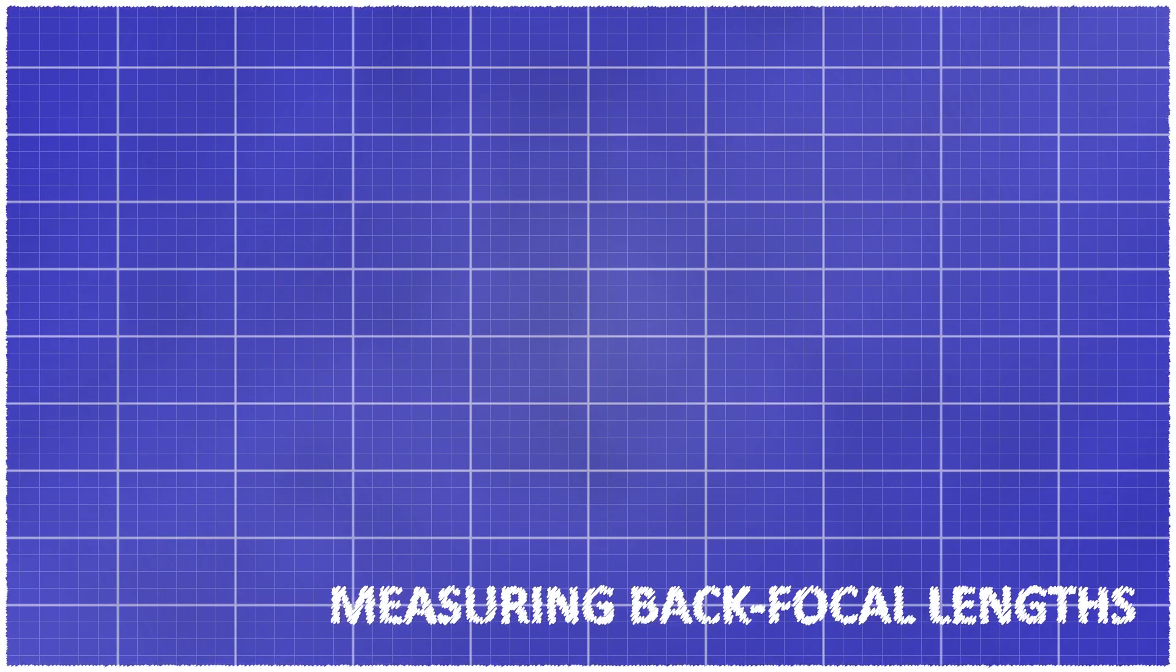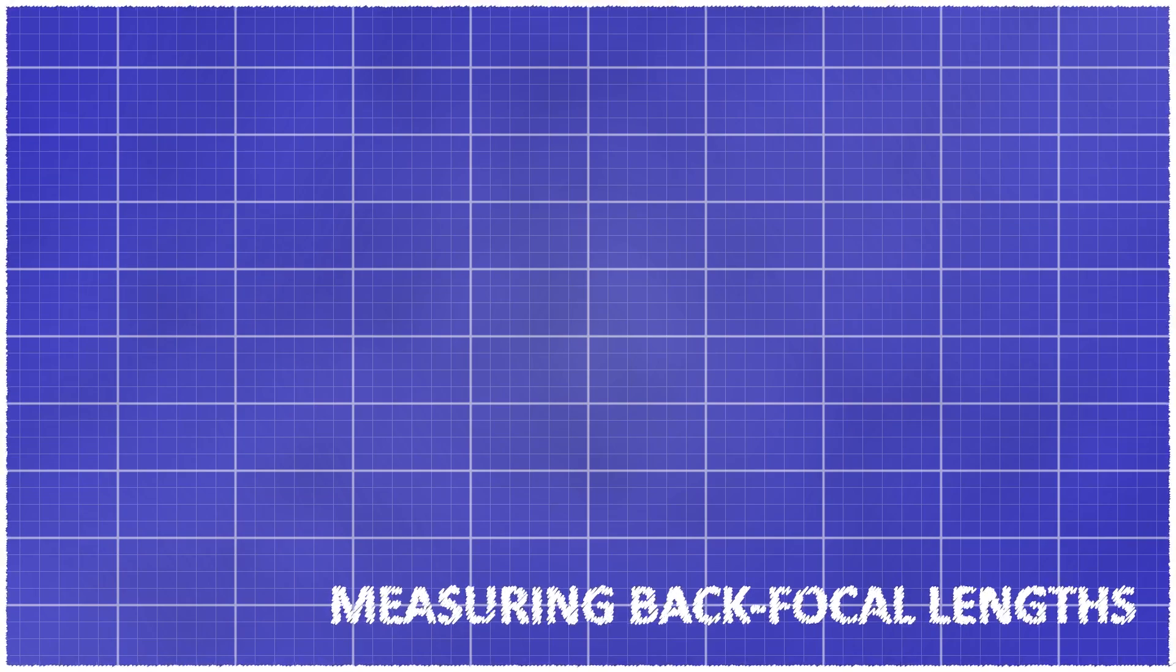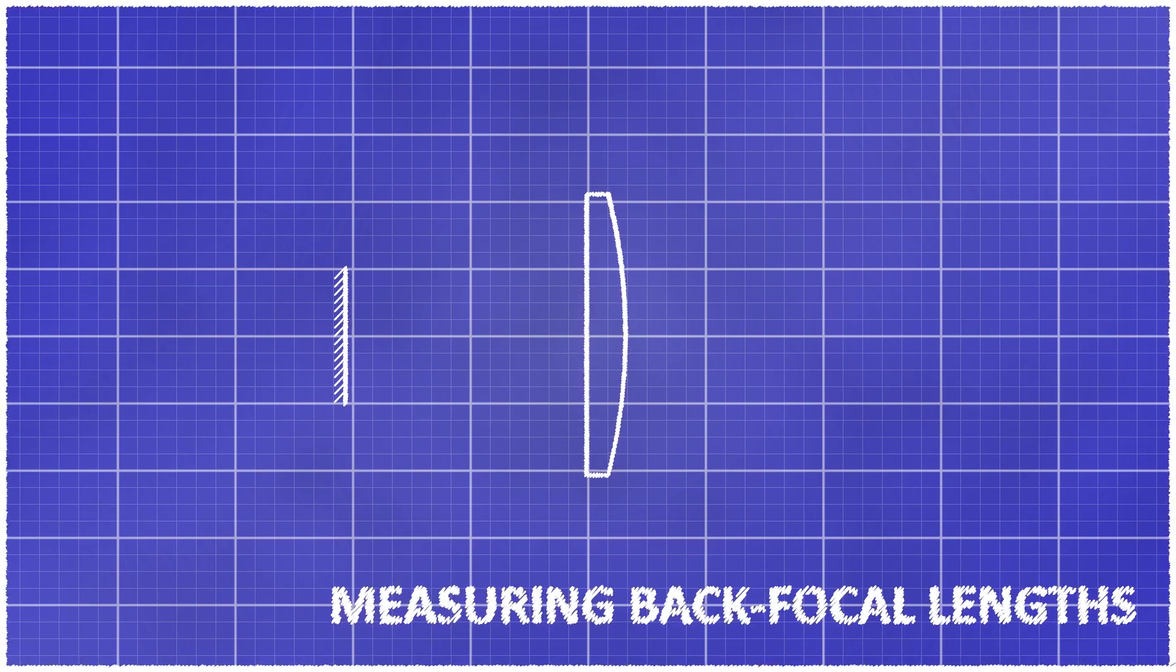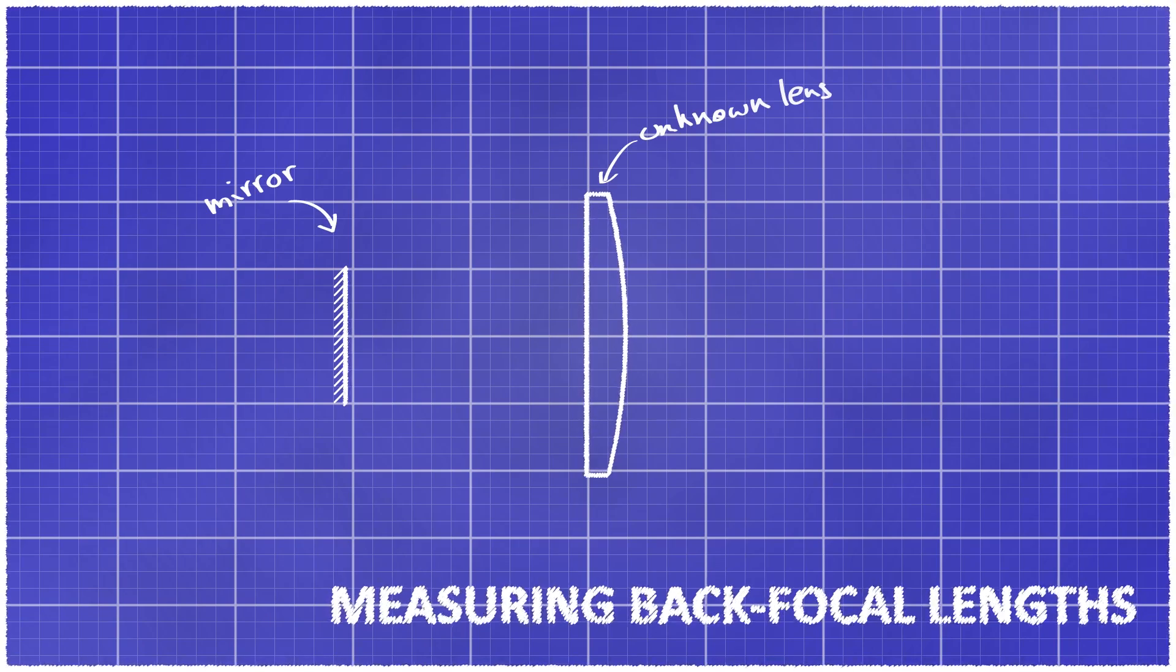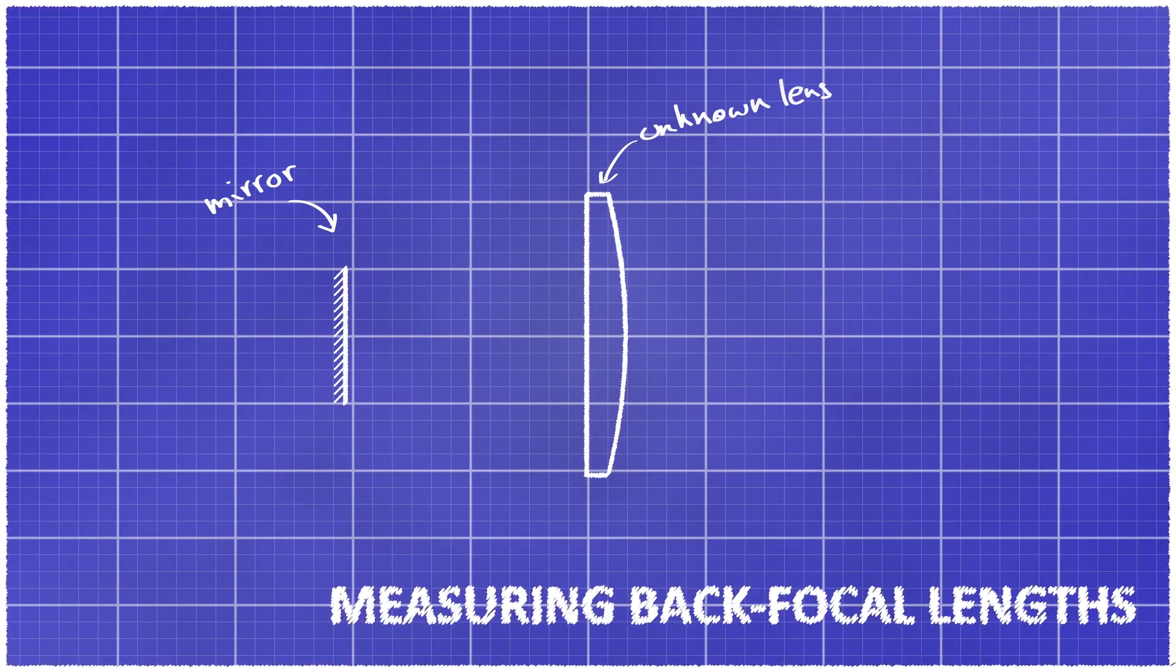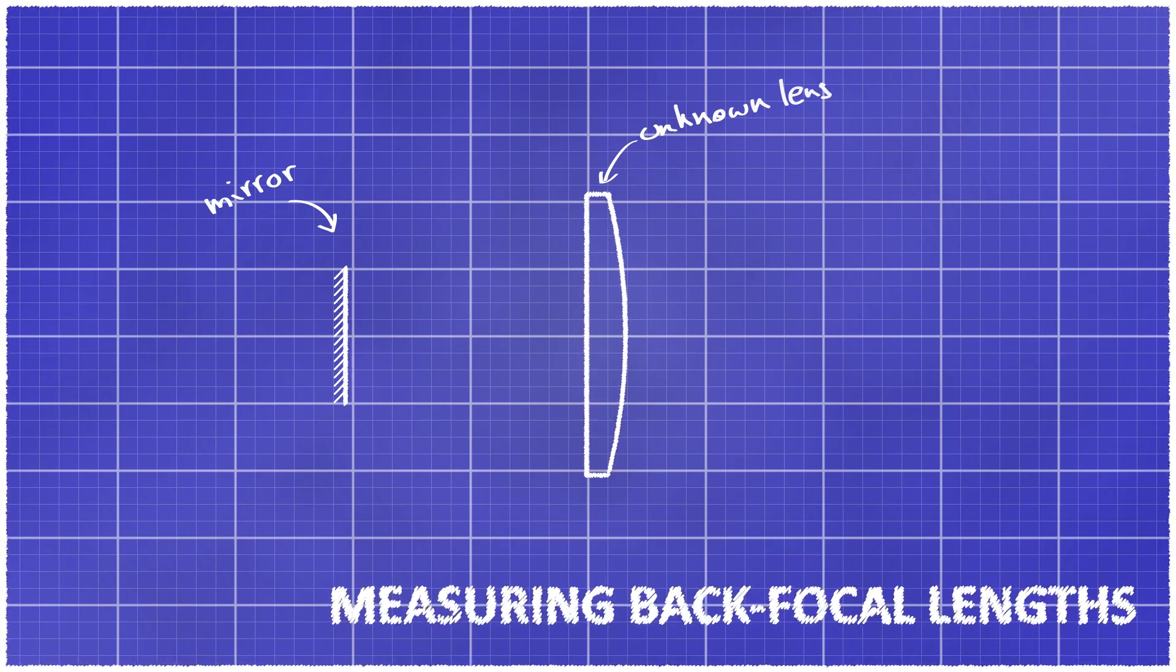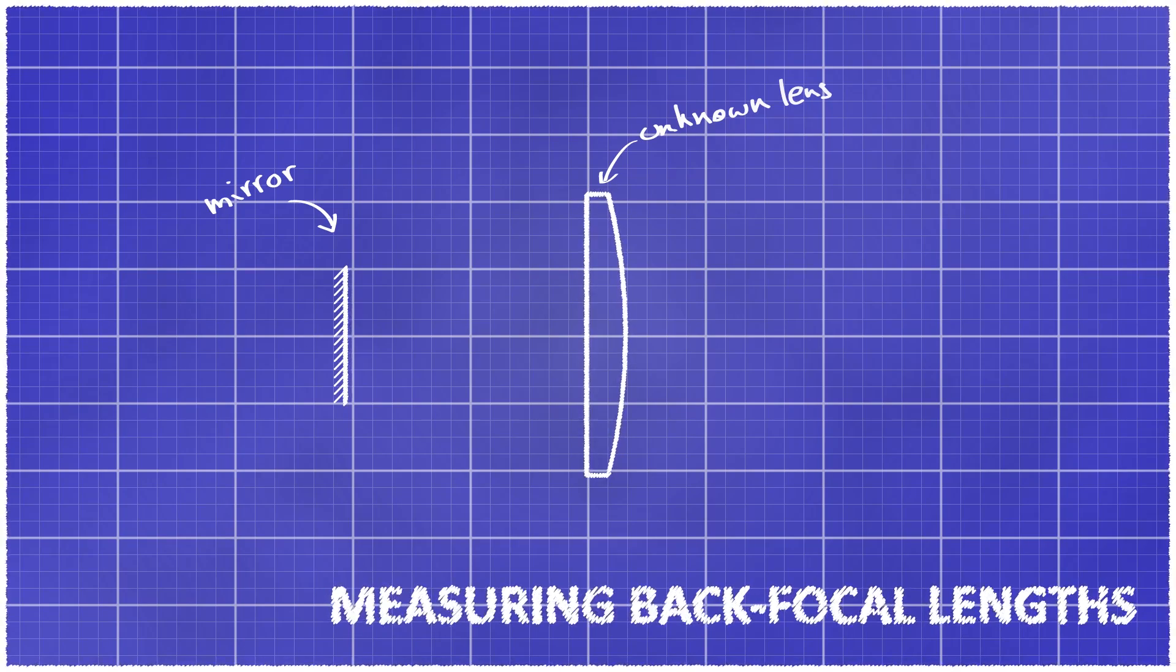A second application is to use auto-collimator to measure focal length. All you have to do is place a mirror behind your lens. Once your mirror is at the exact back focal length position, you will have a cat's eye retro-reflector configuration and the image of the reticle projected by the auto-collimator will be re-imaged sharply on the camera.